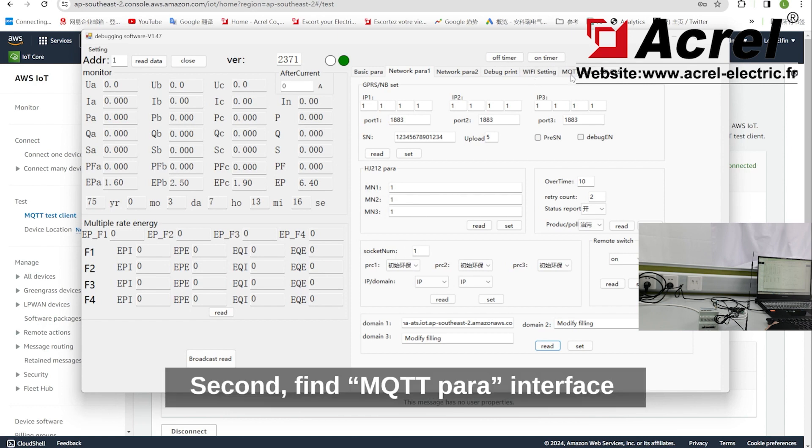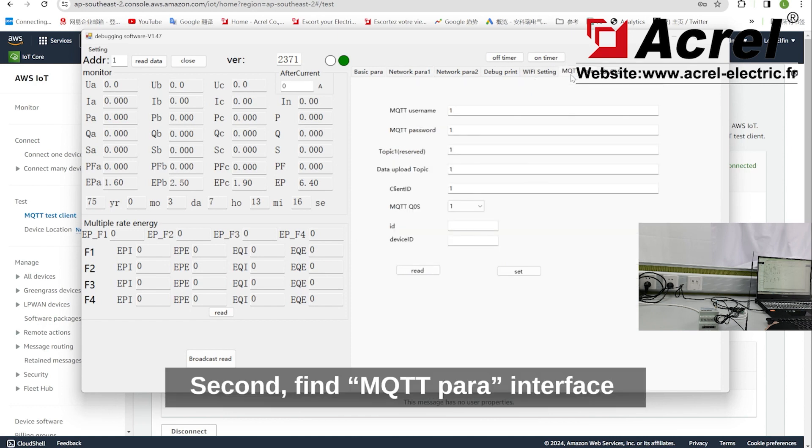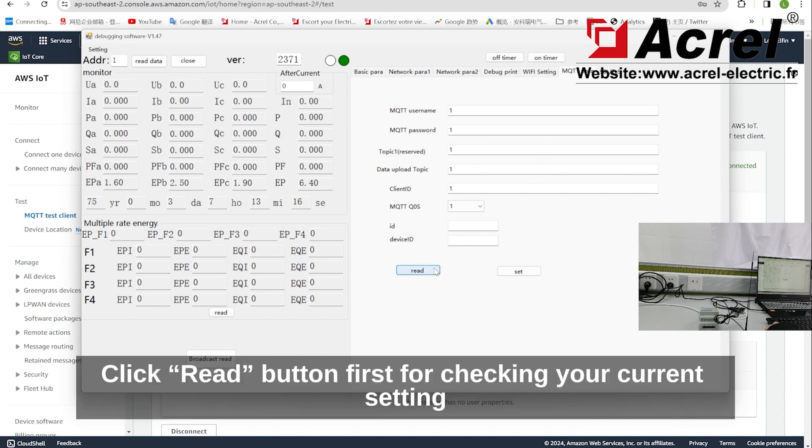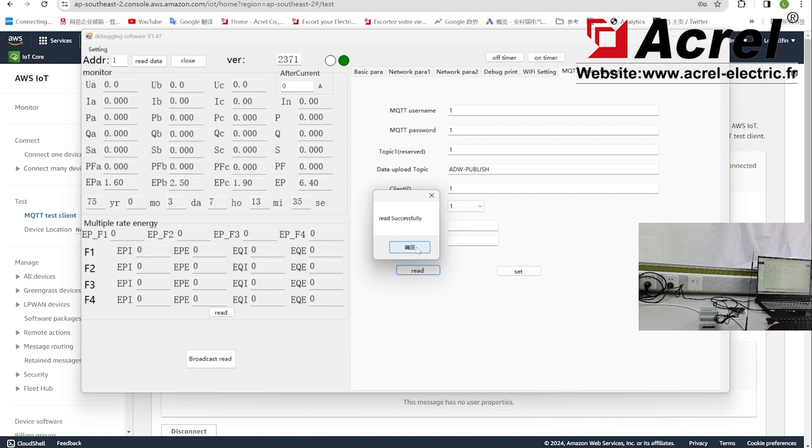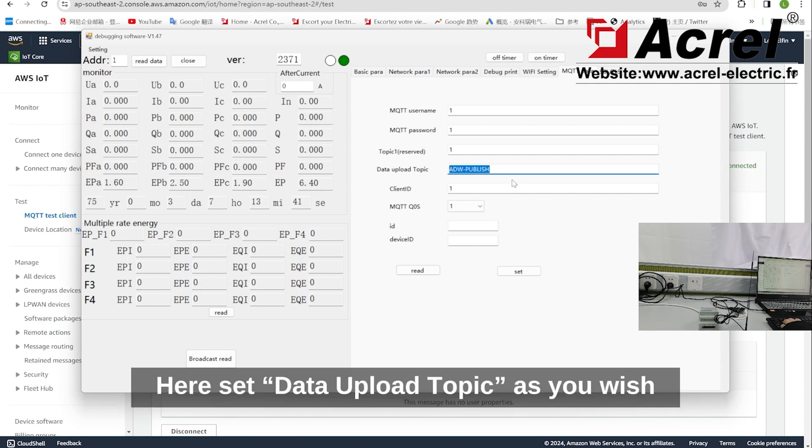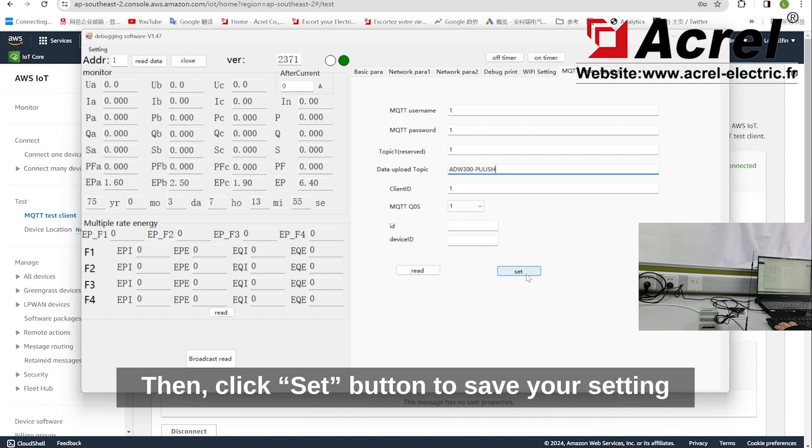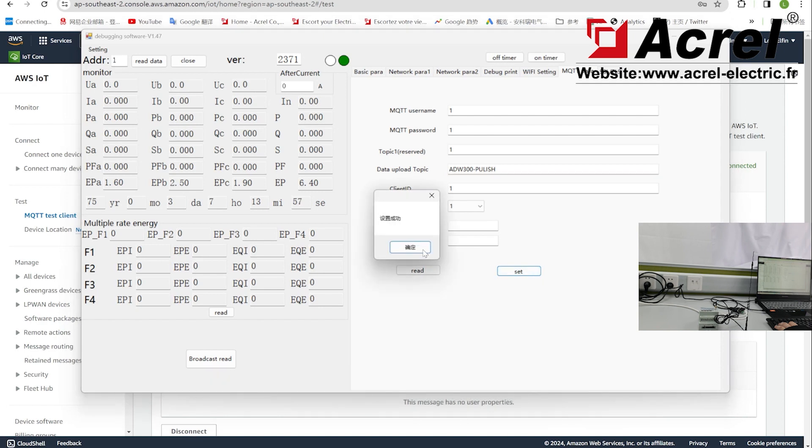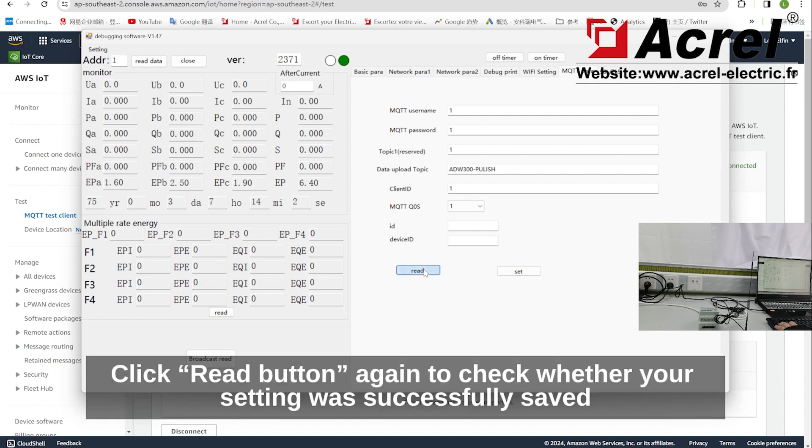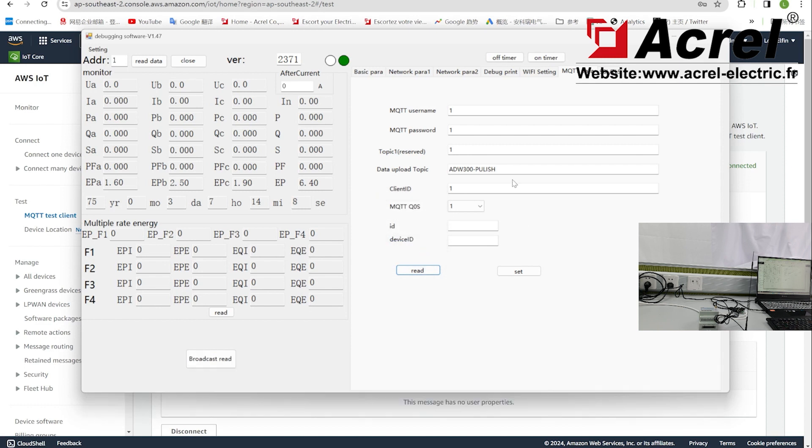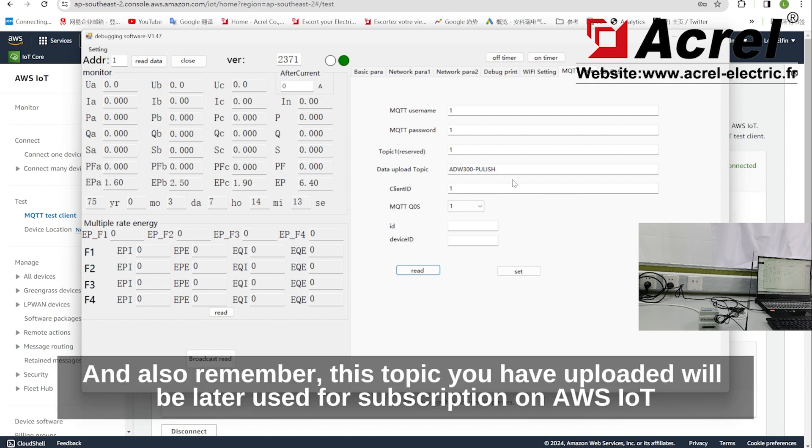Second, find MQTT para interface. Click read button first for checking your current setting. Here, set data upload topic as you wish. I set it as ADW300-publish as a default setting. Then click set button to save your setting. Click read button again to check whether your setting was successfully saved. Also remember this topic that you have uploaded, as it will be later used for subscription on AWS IoT.